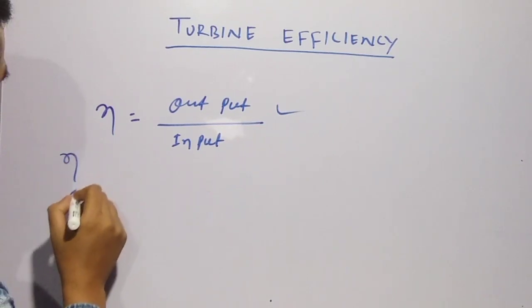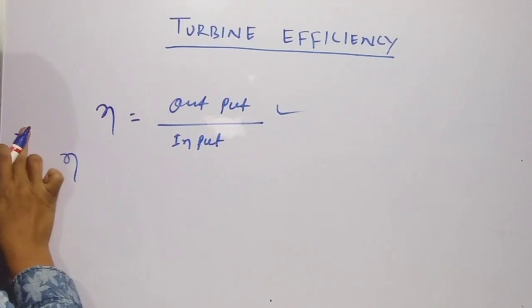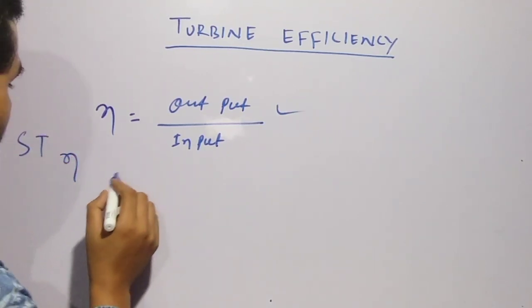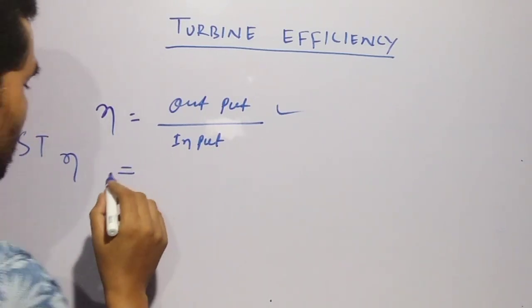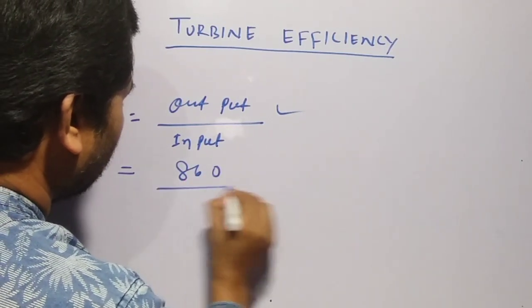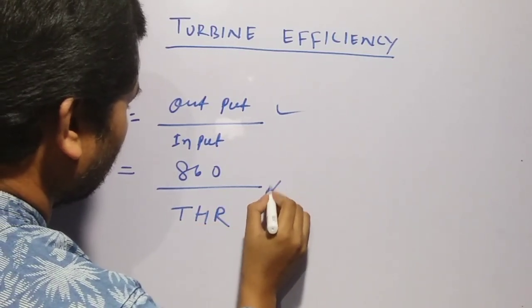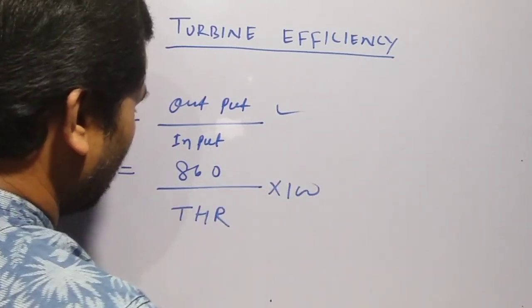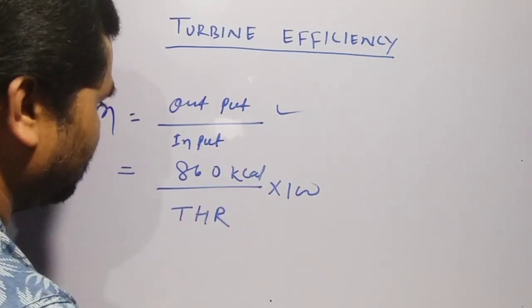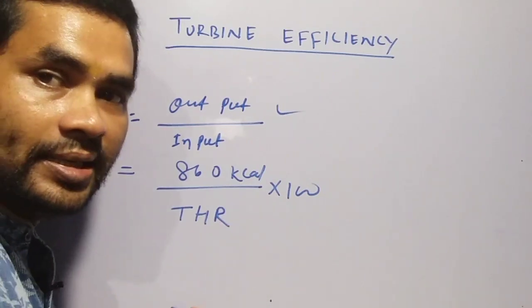For steam turbine, I write: ST efficiency is equal to 860 divided by THR, into 100. Here, 860 is in kilocalories, and THR means turbine heat rate.